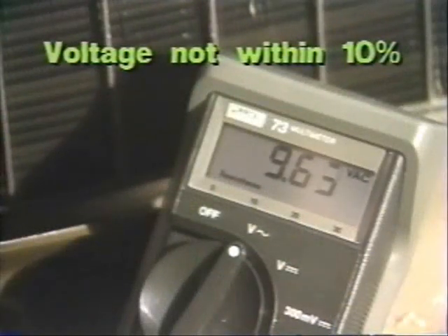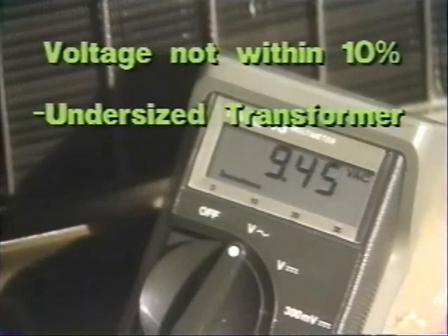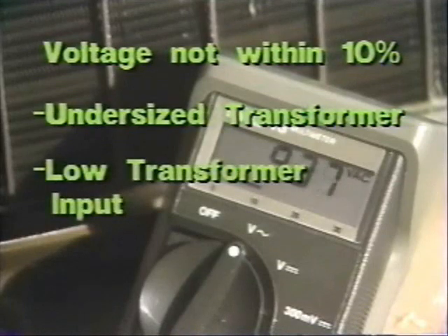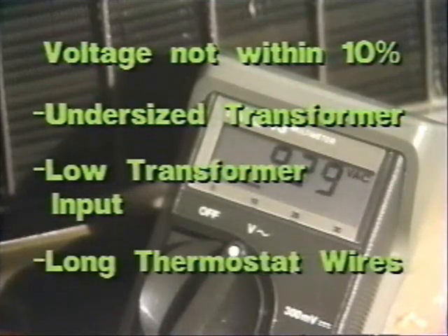If voltage is not within 10%, some possible causes unrelated to the contactor are an undersized transformer, insufficient input voltage to the transformer, or thermostat wires that are too long. These conditions reduce voltage below a coil's operating voltage. To illustrate the effect of improper voltage, we connected a variable voltage source to a contactor. As the voltage increases, it becomes noisy, but the contacts don't close. Increasing the voltage to normal causes the armature to pull in and the contacts to close.